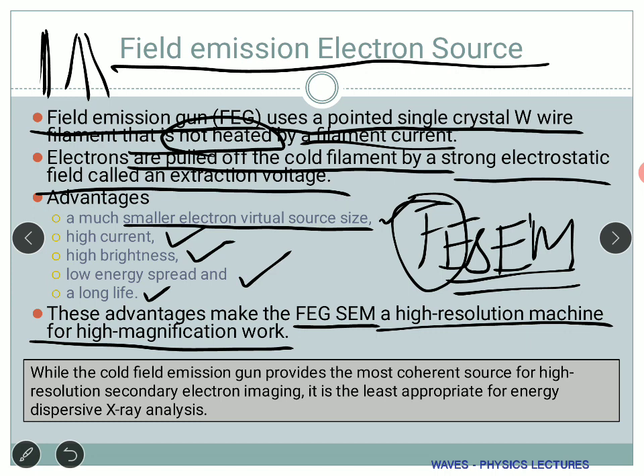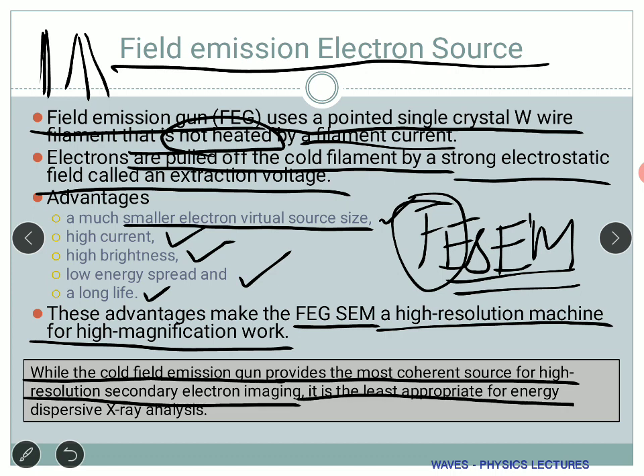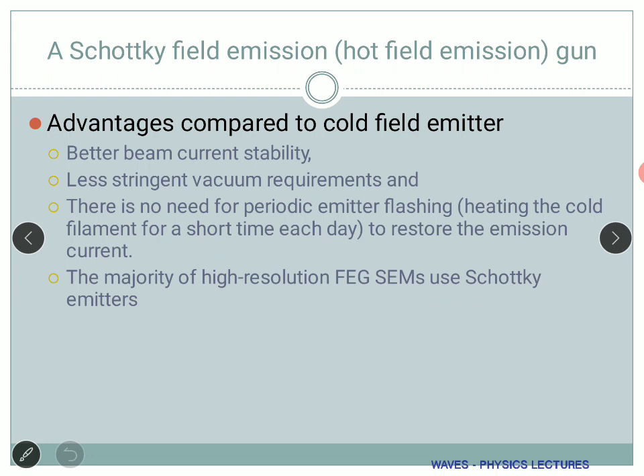Even in field emission electron sources there are two types. One is called the cold field emission gun, kept at room temperature and provided with an electric field — it provides the most coherent source for high-resolution secondary electron imaging, but is least appropriate for energy dispersive X-ray analysis (EDS). For EDS, we use a hot field emission, specifically named the Schottky field emission gun, which combines the field with a heated cathode — temperature is kept high for the cathode while the electric field is also applied.